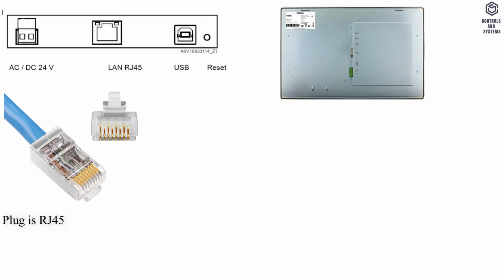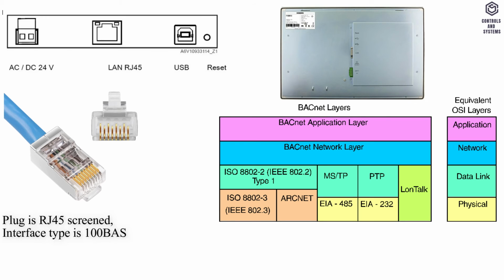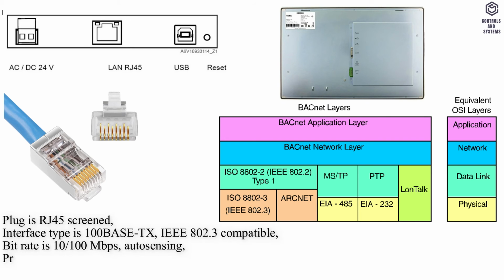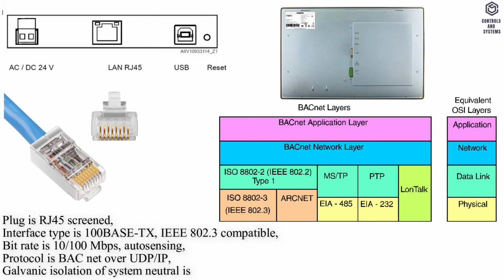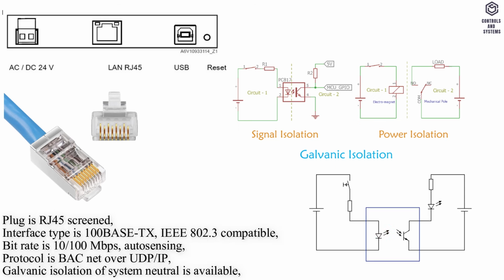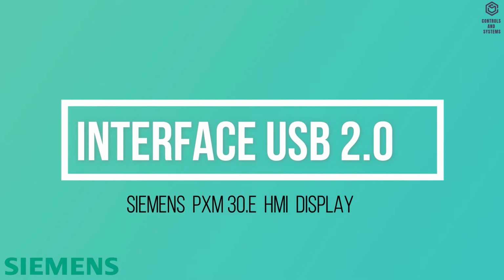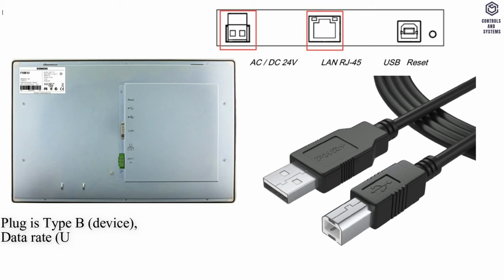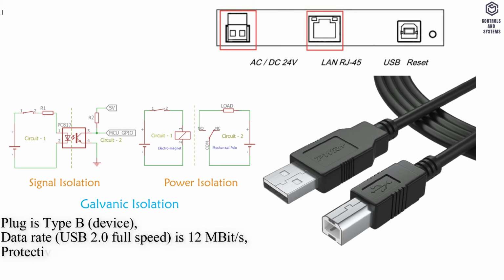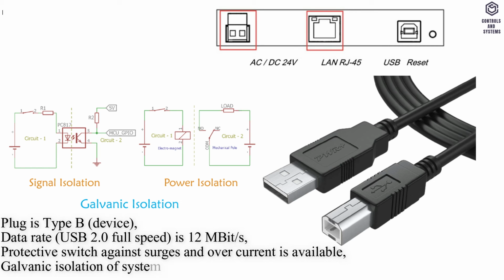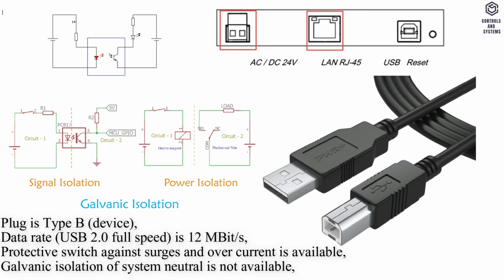Plug is RJ45 screened. Interface type is 100 Base TX, IEEE 802.3 compatible. Bitrate is 10/100 Mbps, auto sensing. Protocol is BACnet over UDP/IP. Galvanic isolation of system neutral is available. Interface USB 2.0. Plug is Type B, device. Data rate, USB 2.0 full speed, is 12 Mbps. Protective switch against surges and overcurrent is available. Galvanic isolation of system neutral is not available.